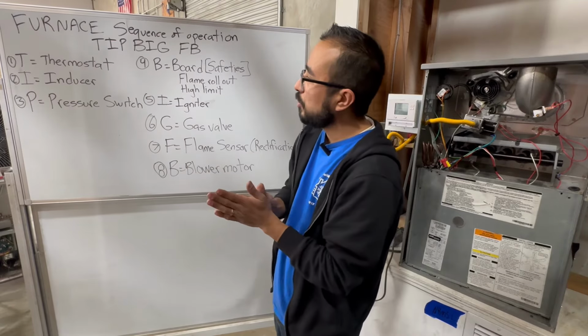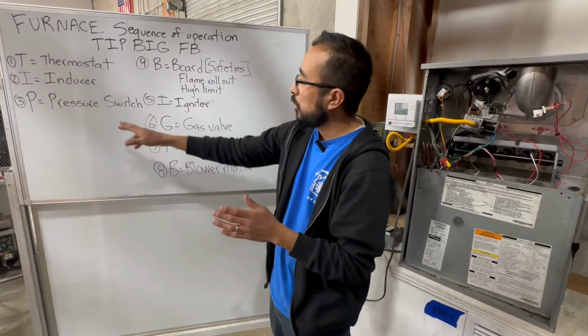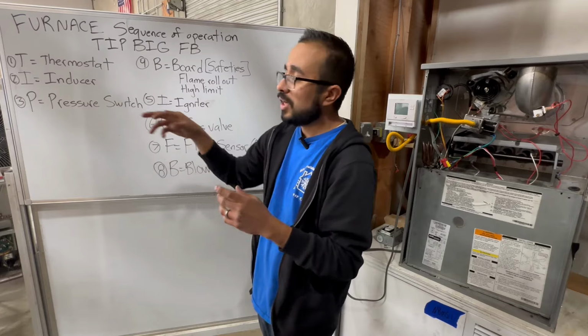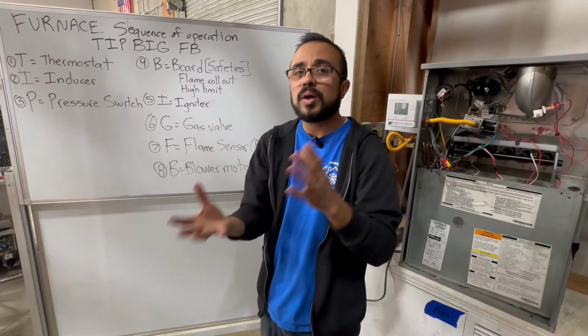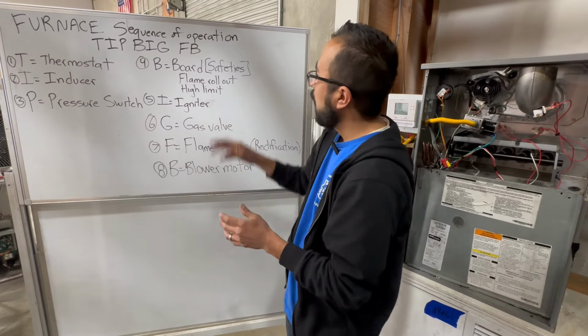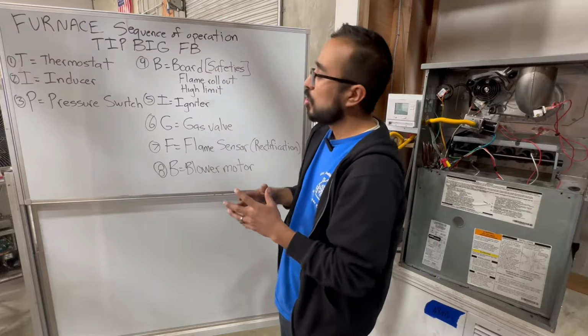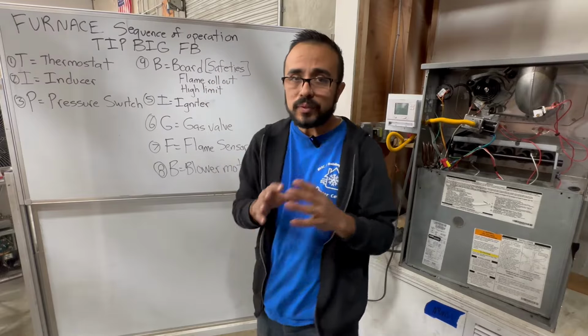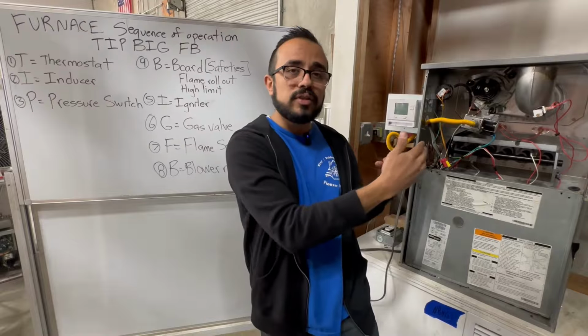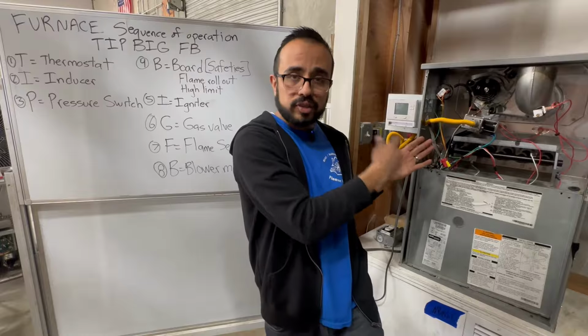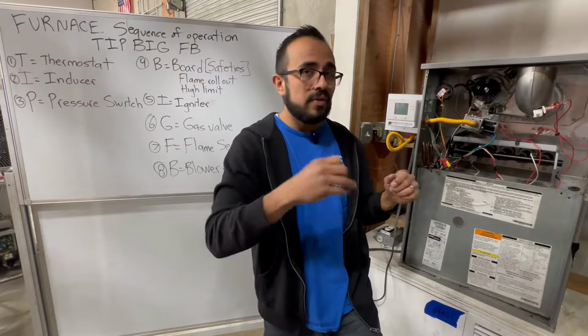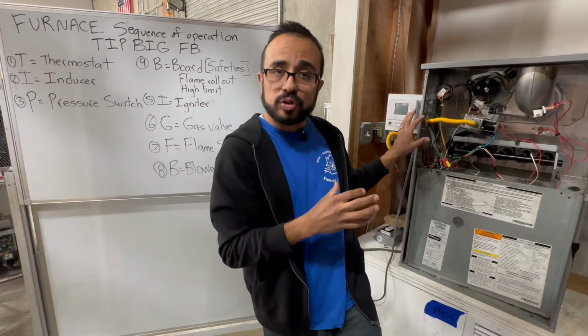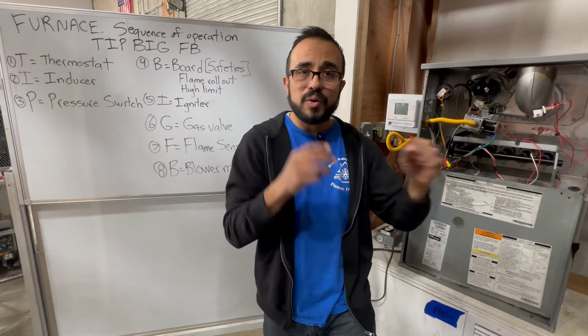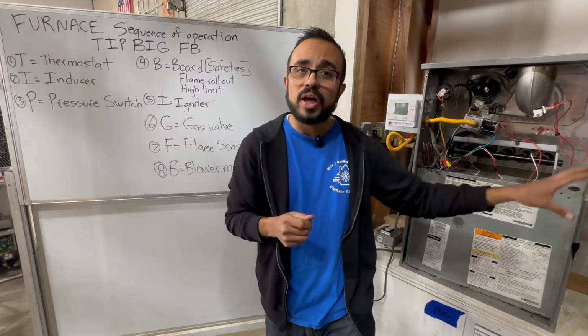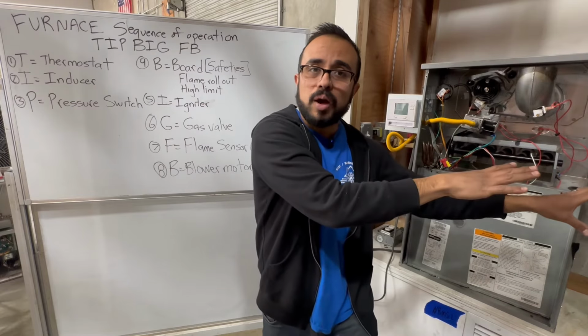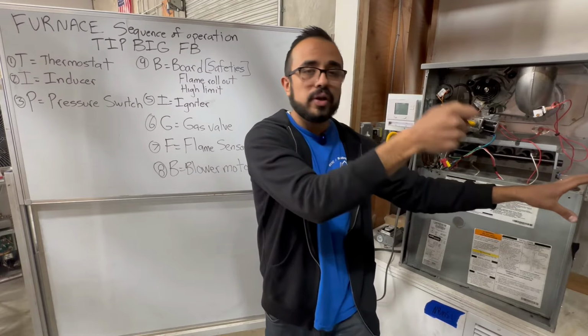Your inducer draft motor receives 120 volts, it turns on. Your pressure switch closes because it's sensing the draft that the inducer draft motor is producing, this negative pressure. And then your board, your safeties must all be closed. It should not be open. Now you were able to see when comparing both furnaces, on this furnace, all the safeties are in series. The rollout, your high limit, if any of them open, it stops sending power to your thermostat. But on the other furnace, even when disconnecting the high limit, your thermostat still had power. It still shut down the furnace from operating, but only the rollout when pulling out the wire did it stop sending 24 volts.